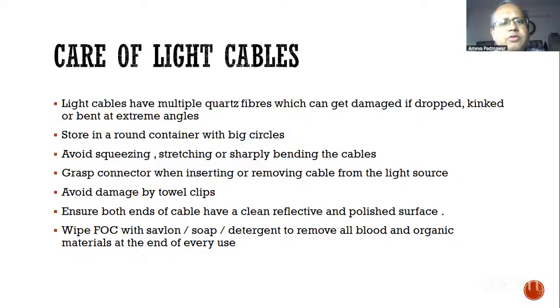Next comes the fiber optic cables. I'm only highlighting those parts which I feel should be brought to the attention of this audience. So when it comes to the fiber optic cables, these are a bunch of quartz fibers, and they are packed inside an armored sheath. And you cannot bend it at extreme angles, because if you bend it, the fiber gets fractured, and one fractured fiber means a fraction of the light transmitted to the optic will be reduced. If there's no light inside the abdomen, nothing gets reflected back, and hence your vision is going to suffer, however great your camera may be.